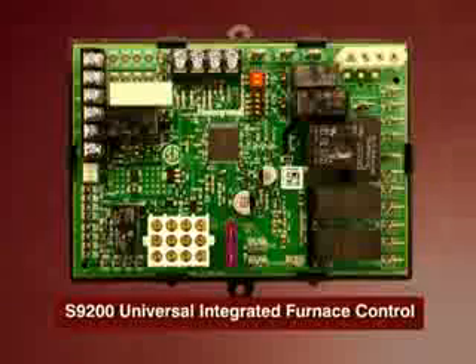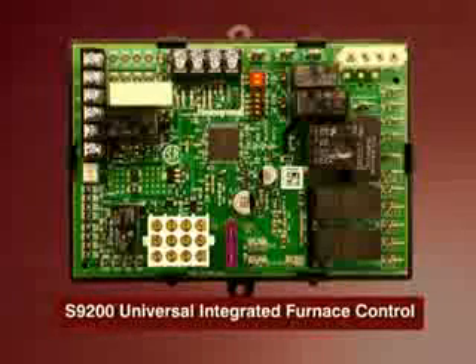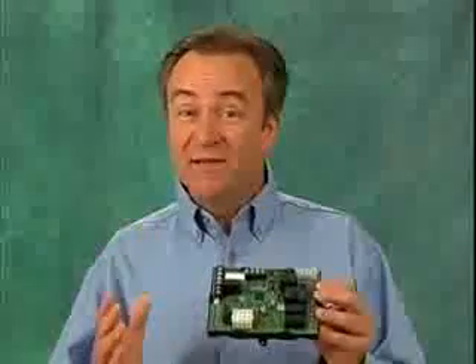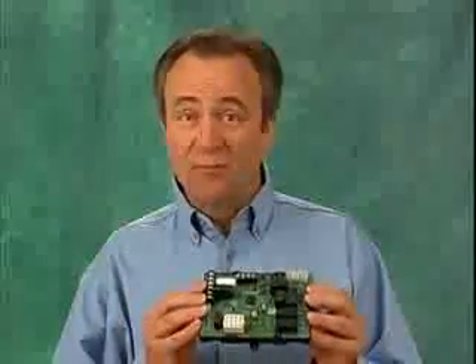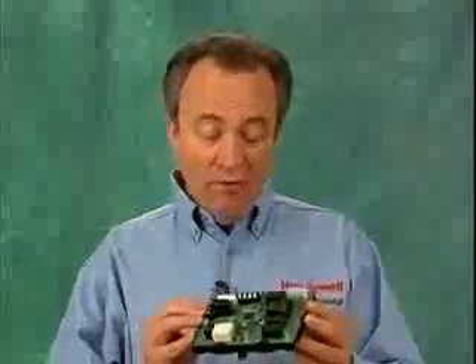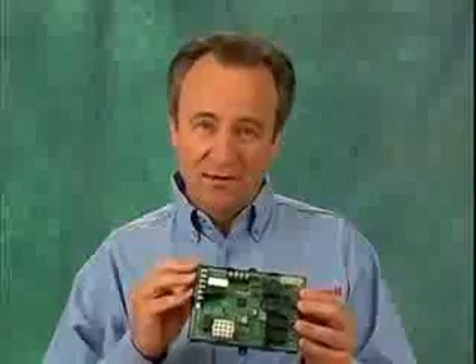I'd like to show you a new service product that Honeywell is currently introducing to the HVAC industry. A universal integrated furnace control. It works with line voltage hot surface ignition equipped single stage gas furnaces and replaces most controls originally installed by the OEM. Over the years, manufacturers have built millions of furnaces with an integrated control similar to this one. Today, it's the most popular way to provide safety and automatic operation for residential gas heating.